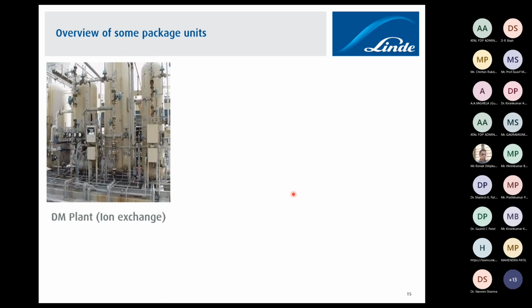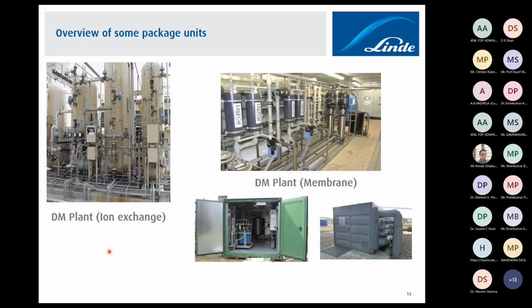Okay, now I will show only some images of similar package units, like a DM plant, an ion exchange based DM plant, and how it looks. As the word suggests, demineralize: we have to remove the minerals from the water which are not in suspension form but in soluble form. All the cations and anions are removed via resin units. Resin is a polystyrene small beads or structure which helps to remove the cations and anions. This is an ion exchange based unit, which typically looks like many vessels and a lot of valves. So this is how a typical DM plant looks.